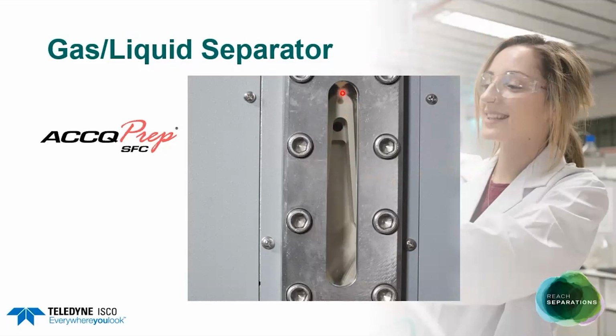The first stage of the process is an impact separation against the glass surface in front of us. What happens next is then the mixture is accelerated around these fins around the outside of the GLS, which then creates a cyclone effect, resulting in the CO2 gas being exhausted at this point here. What you're then left with is your analyte and your remaining CO2 co-solvent, which is forced out of the GLS at the bottom just here and onto your fractionation valve. And if I run the video for a short period of time, you'll see solvent coming up in the top and being expelled out of the bottom.